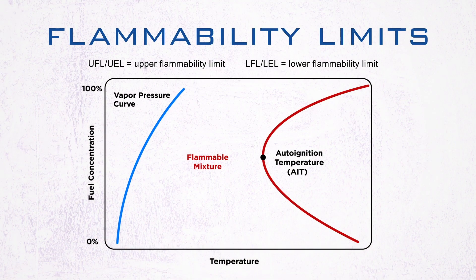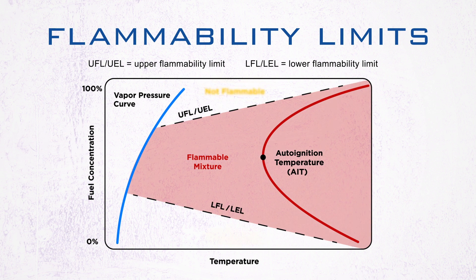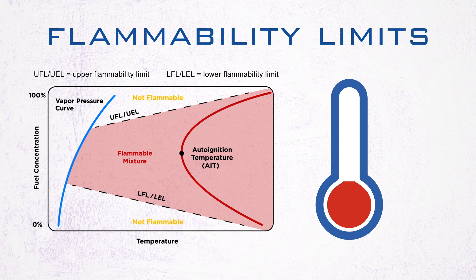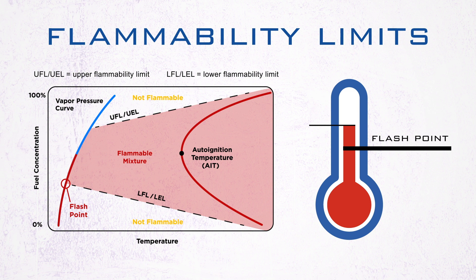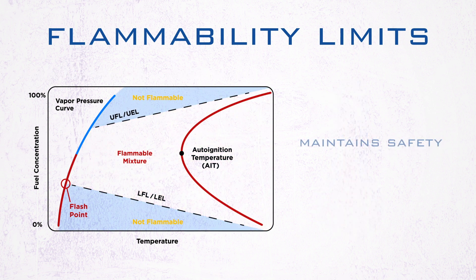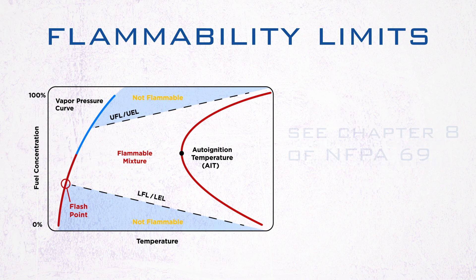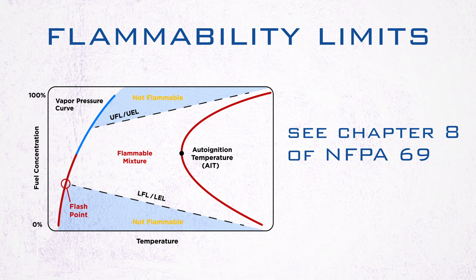Flammability limits: you've got your LFL and your UFL. The flammable region begins and ends between the two. In order to conduct an LFL test, the chemical must have a flashpoint and the temperature of the testing environment must be above it. Knowing these limits is valuable because operating close to, but outside of them, maintains safety while also potentially keeping product yields high. Chapter 8 of NFPA 69 advises the permissible safety margin necessary when operating near the flammability limits.